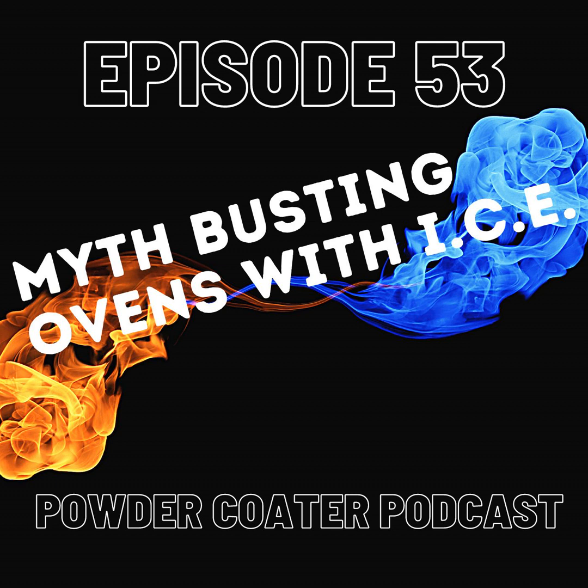Right. In fact, most of the manufacturers who only do infrared, for example, over the years, and I've seen it much more so over the last 5 years, they've actually gone to, you could almost call it a hybrid. Because it used to be they built all the infrared ovens and there was no air circulation other than a little bit of exhaust. Now, all of a sudden, they've got ductwork in there and they're moving a lot of air, trying to help conduct that heat across the part and to minimize banding and some of the other issues you get depending on the density of your elements.